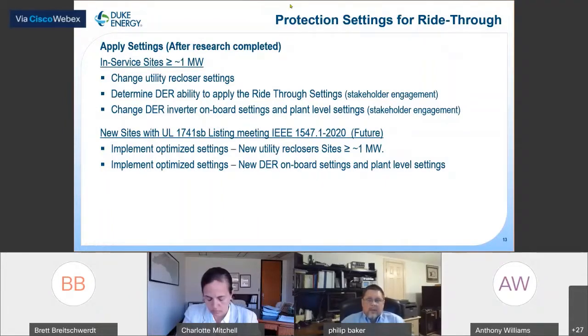Two areas to mention here: in-service sites and new sites. For in-service sites, we are mainly focused on sites at 1 megawatt and above. Those are the sites that typically have a utility recloser, so we do have to visit those sites and put new settings in them.